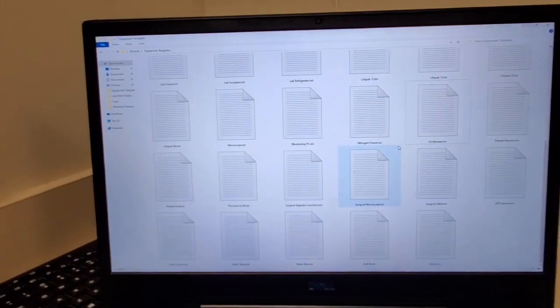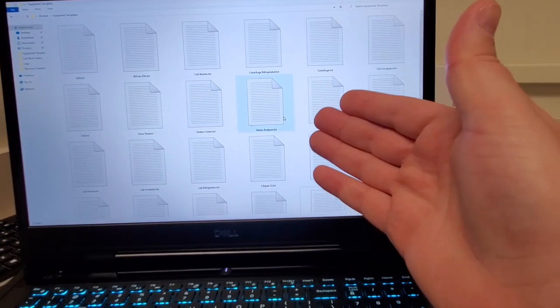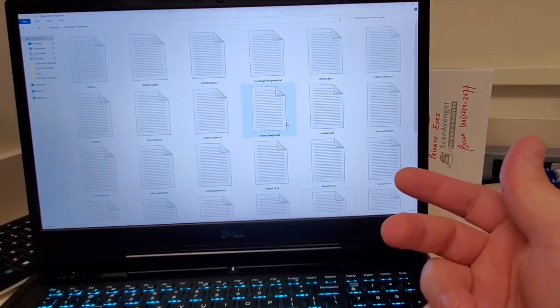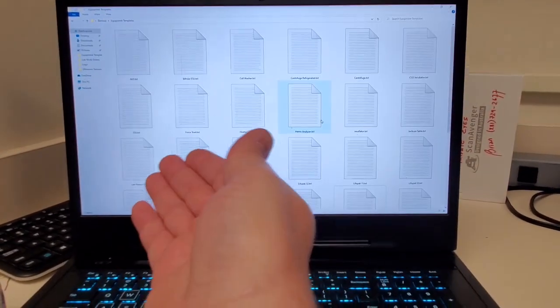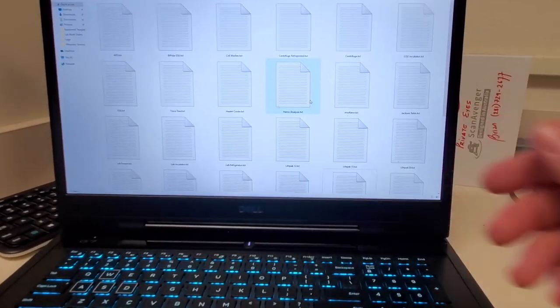So these are my notes and this is how I curate the list — I have all my notes for the different models and different types of equipment that I've done. They're kept in a folder on my desktop under a Biomed folder, kept separate from personal stuff. I keep some of them specific if there are very specific tests. Like I have one for the Jackson table, because it's not a typical surgical table — there are two mechanical actuator lifts on each end, plus you check the frame in the middle, completely different than a standard surgical table.